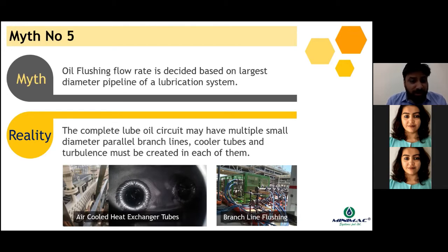Hence, it's very important to check the complete lube oil circuit, and not to follow only what your client has advised. A lot of times the clients would say that the largest size of the lube oil system is 4-inch. So you as a contractor, as a service provider, would calculate the Reynolds number based on the viscosity for a 4-inch diameter pipeline. When you reach the site and start the flushing, you understand that 4-inch was just the manifold line, but there were maybe around 7 to 8 1-inch or 2-inch diameter branch pipelines where your flow would get divided, because you have to perform flushing in a fast track manner. Thereby you would end up feeding just a 10th or a 20th of the demanded flow rate for these branch pipelines. Thereby your flushing would be improper.